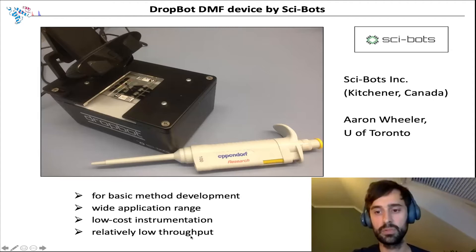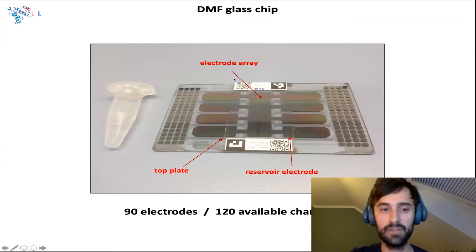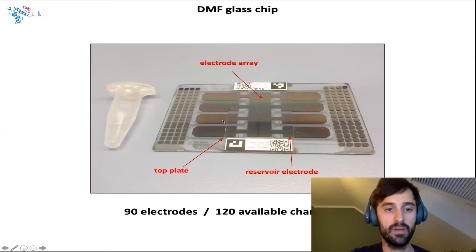We also purchased glass chips from Sci-Bots. These are actually produced in a clean room. They have 90 electrodes you can use, but the DropBot has the capacity to actuate 120, so there is room for more. Of these 90 electrodes, we have eight reservoir electrodes where we can load samples into the chip.